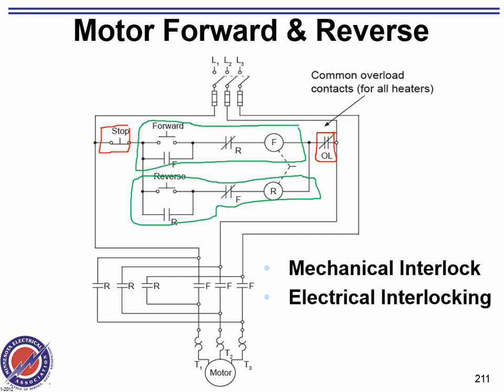the starting mechanism. You stop the motor either way. The other tricky one is when you reverse a three-phase motor, guys, we flip two phases. Okay, so we need so-called electrical interlocking. Can you guys see that? In the forward control circuit, you cannot go reverse while it's going forward.